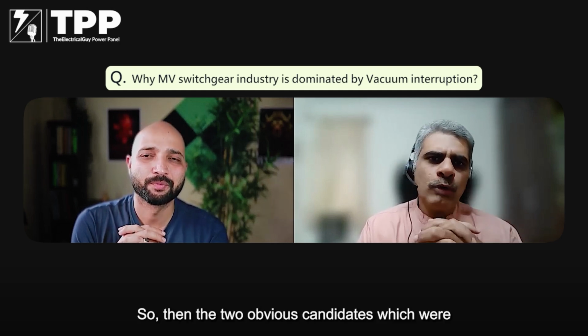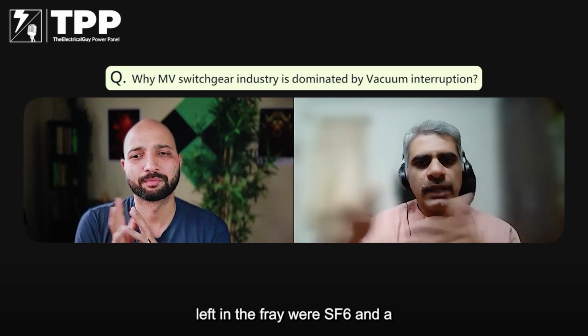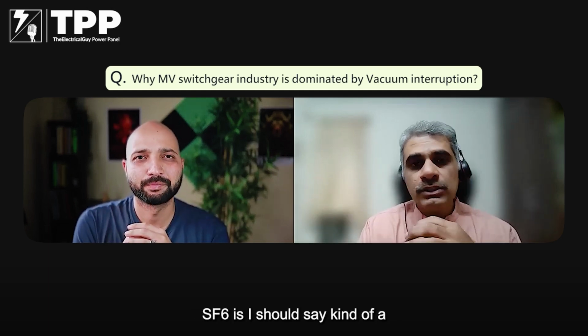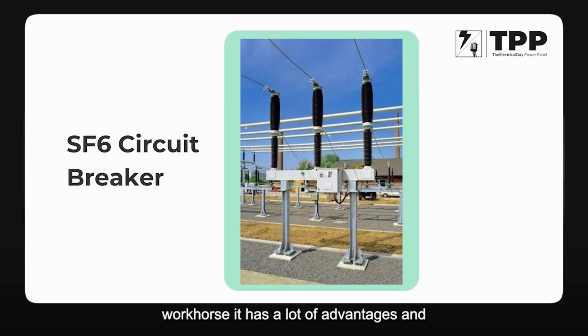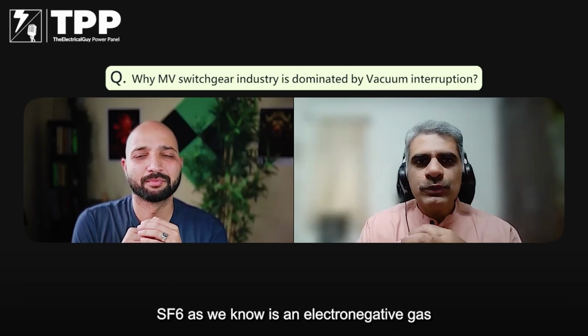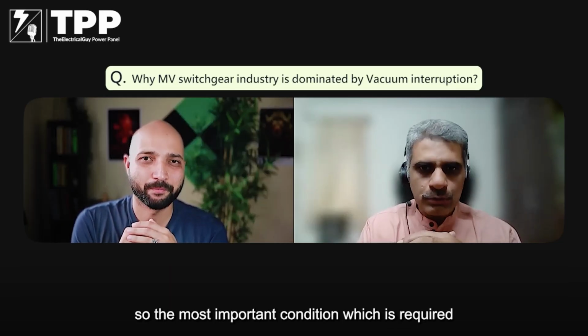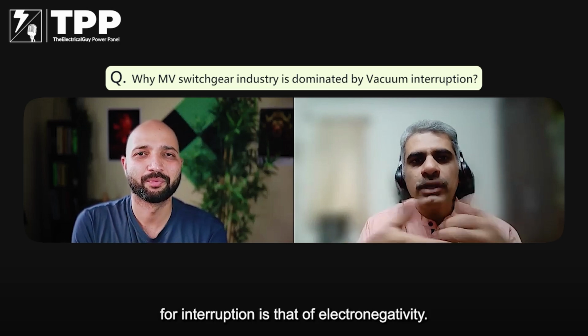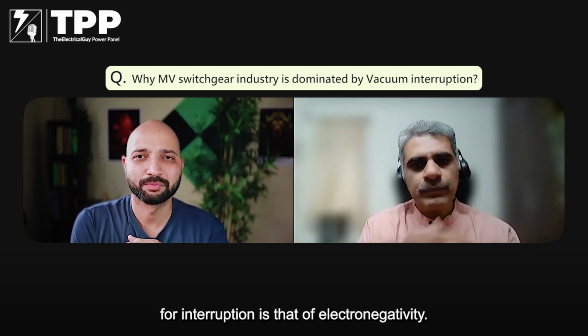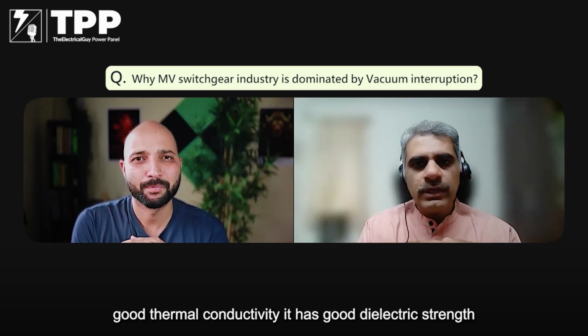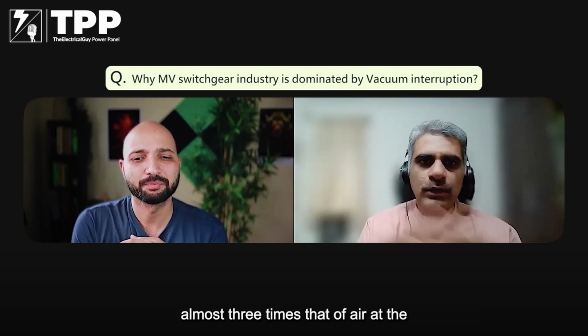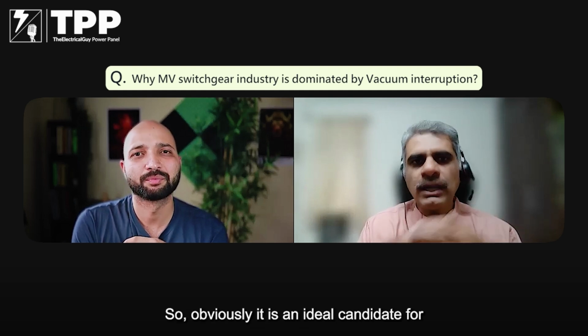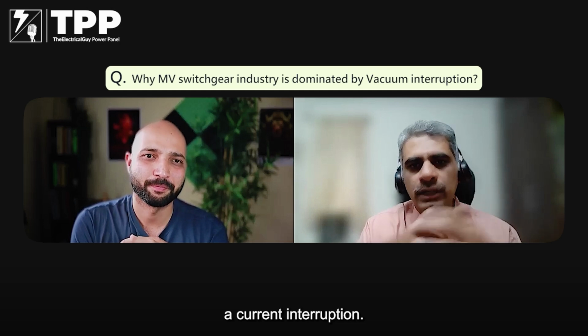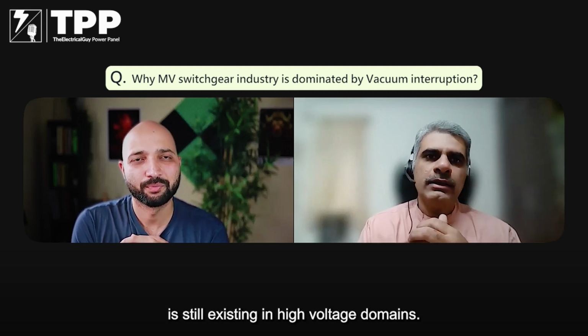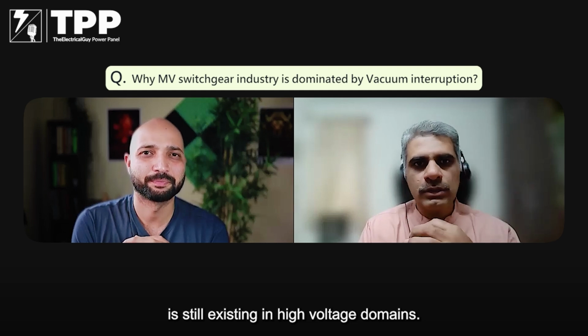So the two obvious candidates left in the fray were SF6 and vacuum circuit breakers. SF6 is, I should say, kind of a workhorse. It has a lot of advantages, and it's a very reliable technology. SF6, as we know, is an electronegative gas, and the most important condition required for interruption is electronegativity. It takes away all the electrons. It has good thermal conductivity and good dielectric strength, almost 3 times that of air at the same pressure. So obviously, it is an ideal candidate for current interruption. That's why it existed, and it still exists in high voltage domains.